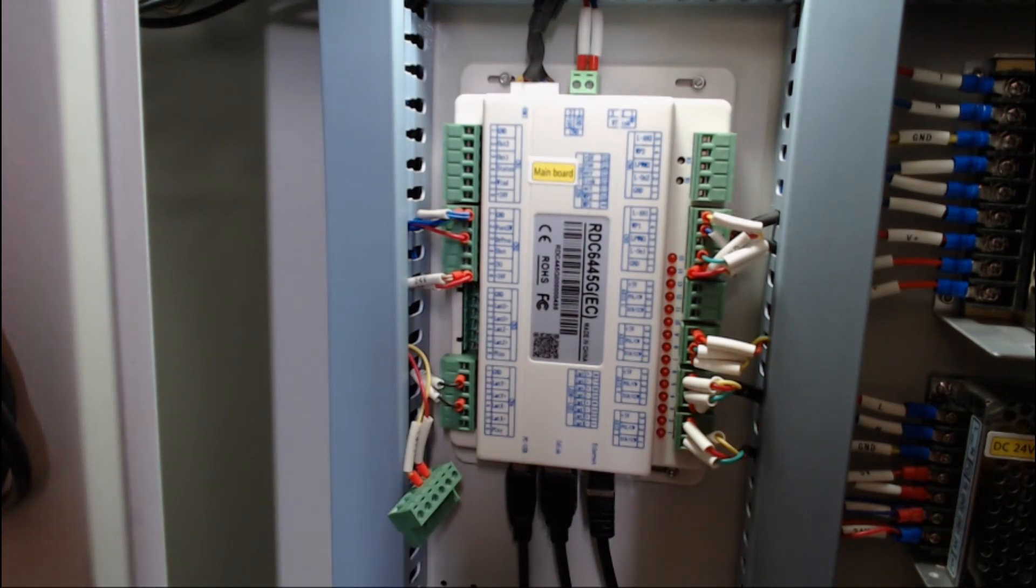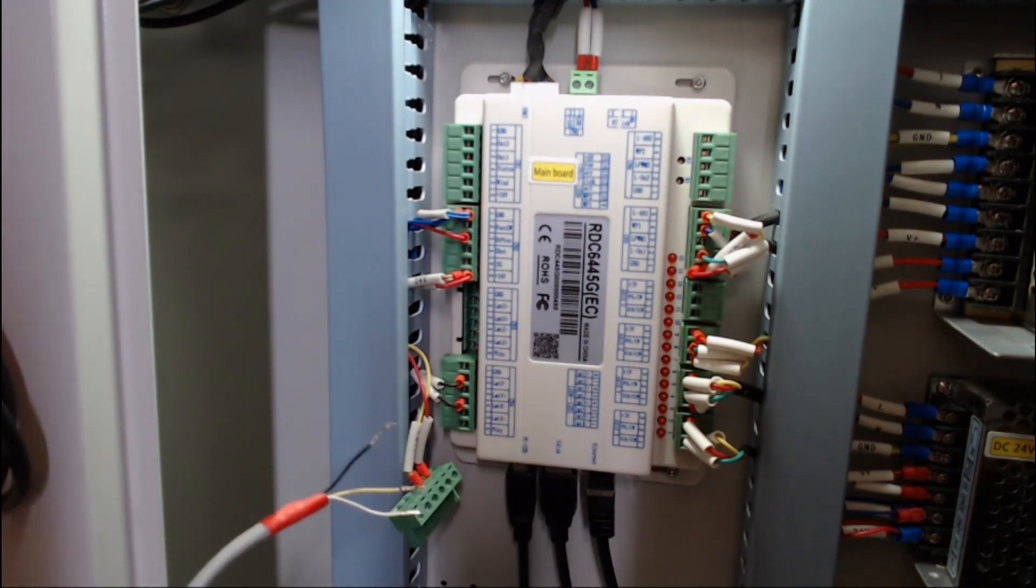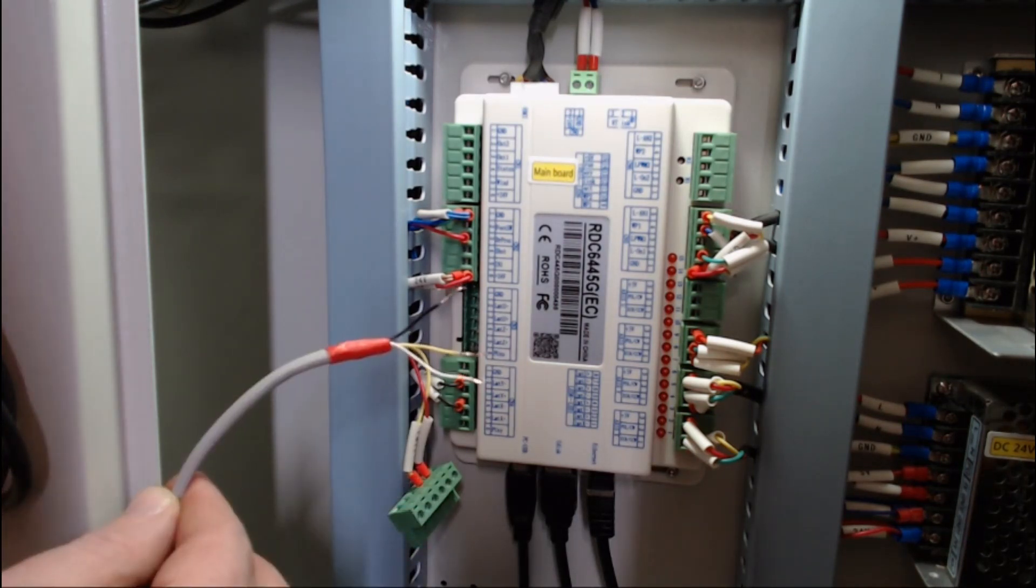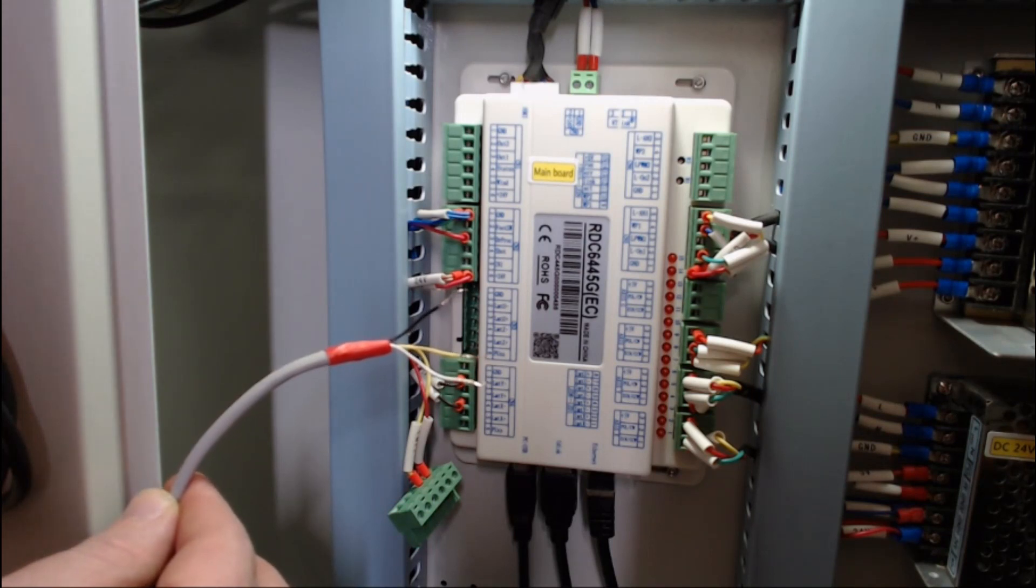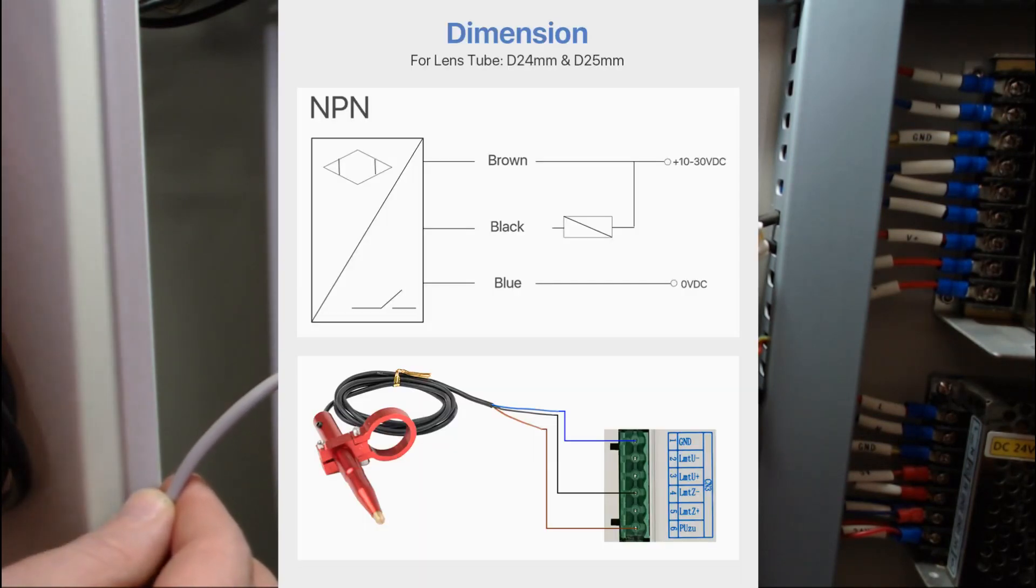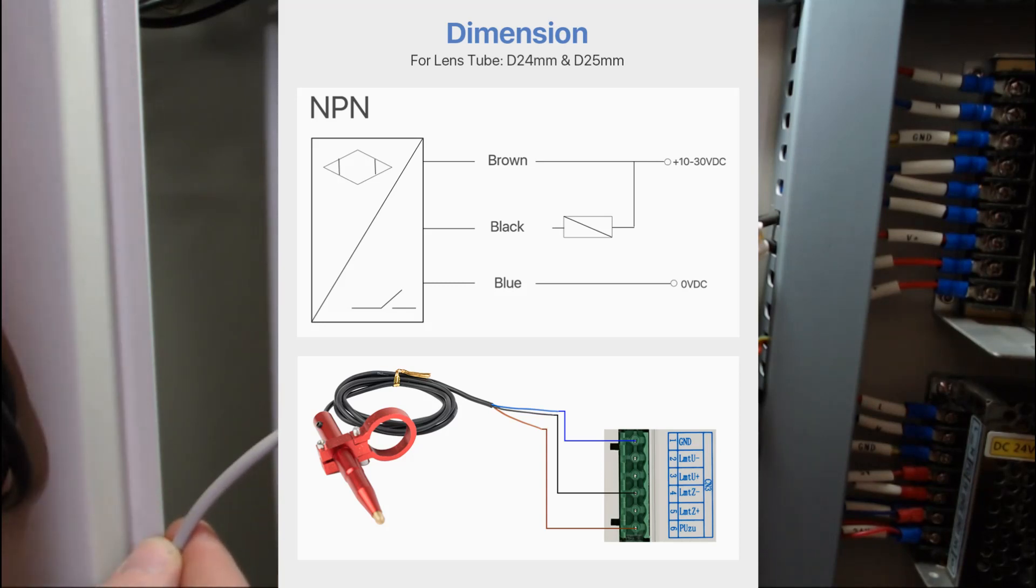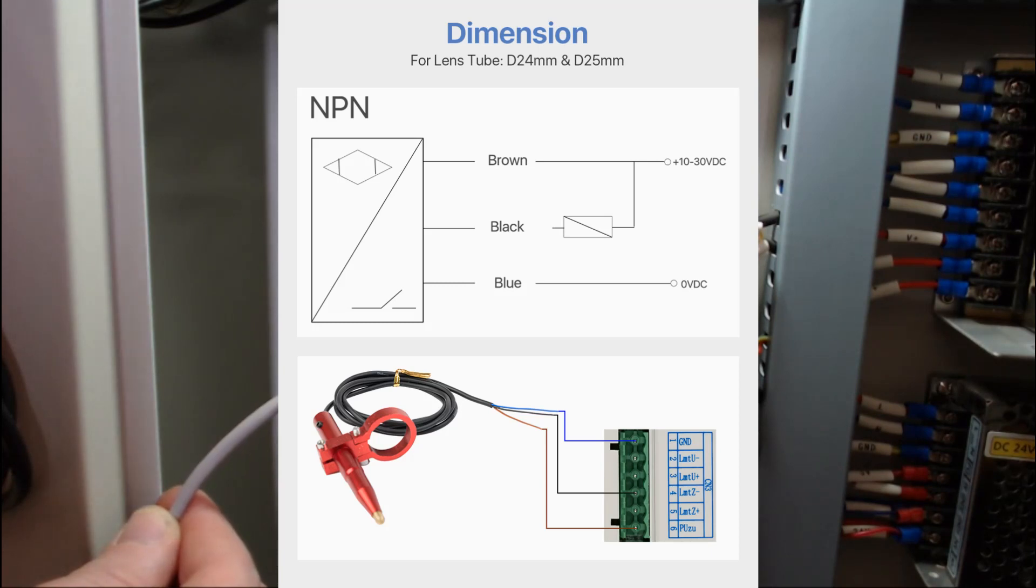Now the wires that we ran down from the sensor switch—I'll pop a wiring diagram up on the screen—the black cable goes into pin four, the brown cable goes into pin six, and the blue cable goes into pin number one.